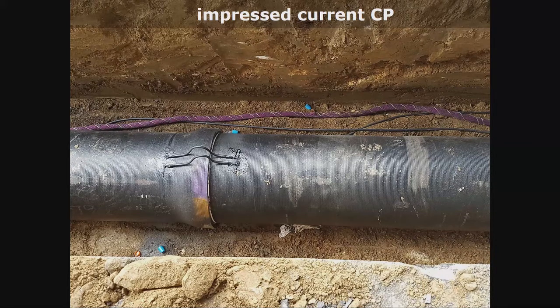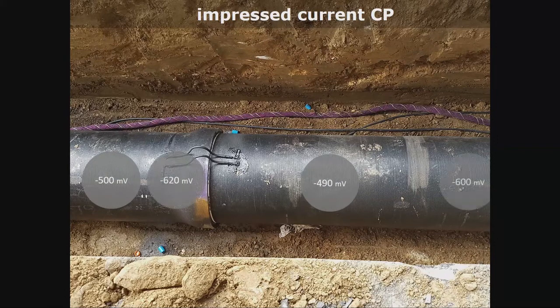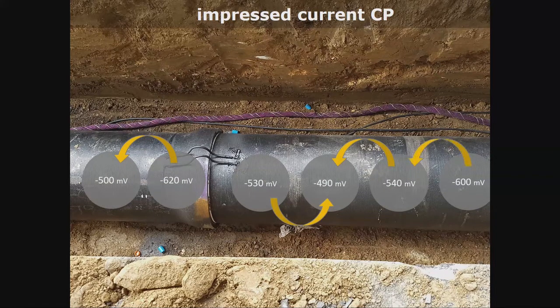So how do we know that it works really well? Well, remember we talked about millivolts? If you have a path that these electrodes are going on, think of this as a little bit of a sprinkler of energy that's going from path to path, and it'll leave at the lowest one. It'll leave at -525 for ductile. So what do we do? We redirect that path. We change the direction. What are we doing when we're doing impressed current?